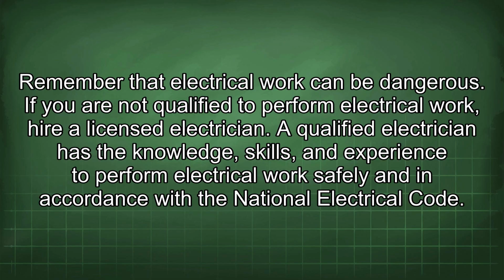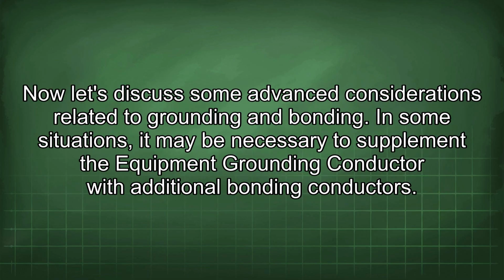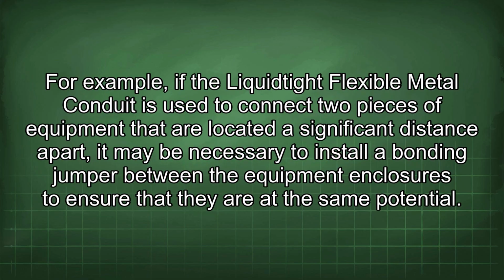If you are not qualified to perform electrical work, hire a licensed electrician. A qualified electrician has the knowledge, skills, and experience to perform electrical work safely and in accordance with the National Electrical Code. Now let's discuss some advanced considerations related to grounding and bonding. In some situations, it may be necessary to supplement the equipment grounding conductor with additional bonding conductors. For example, if the liquid-tight flexible metal conduit is used to connect two pieces of equipment that are located a significant distance apart, it may be necessary to install a bonding jumper between the equipment enclosures to ensure that they are at the same potential.